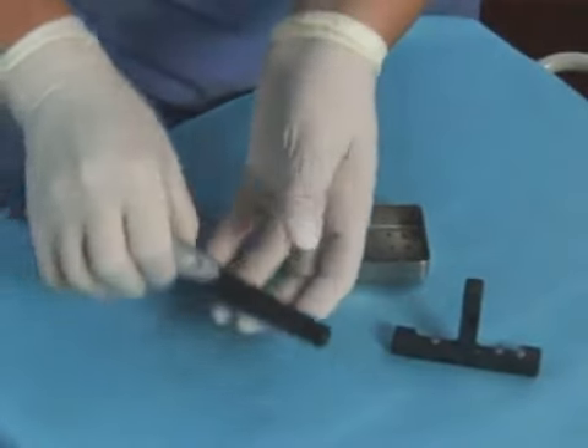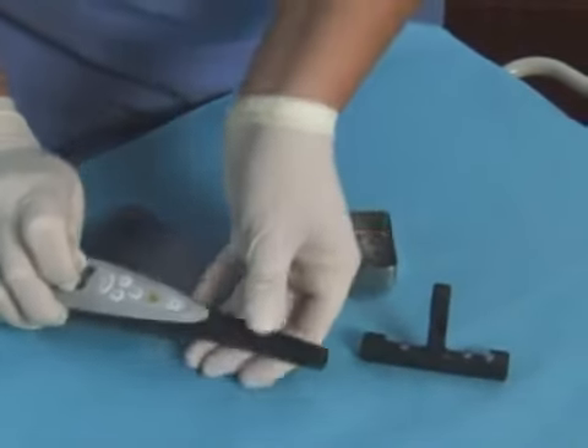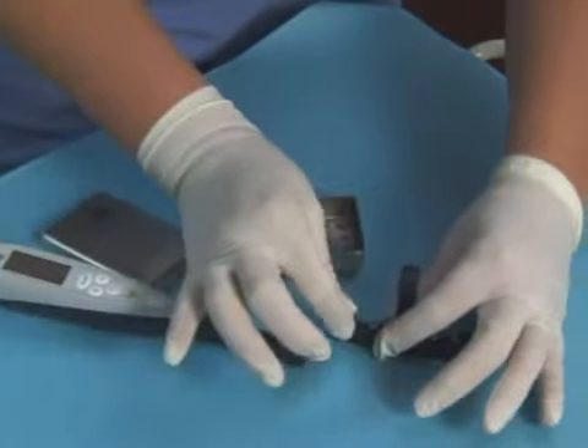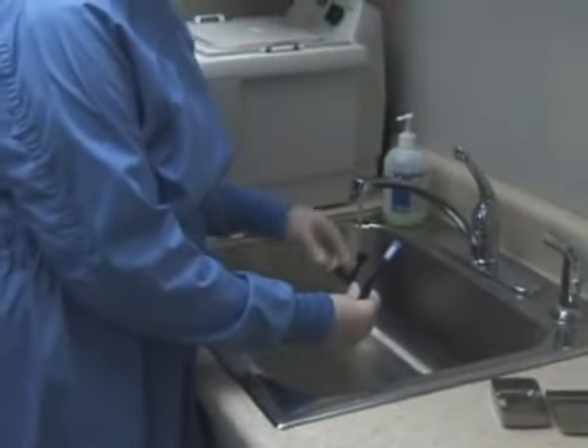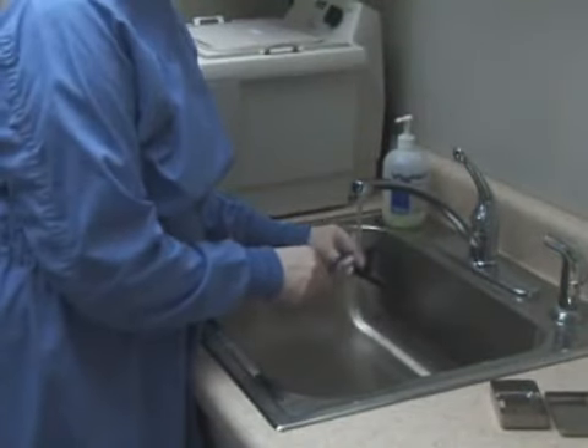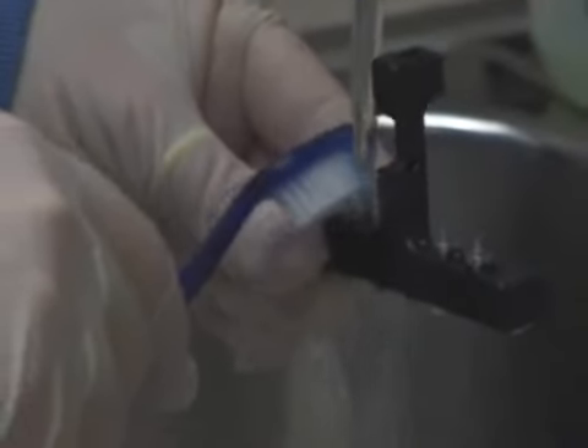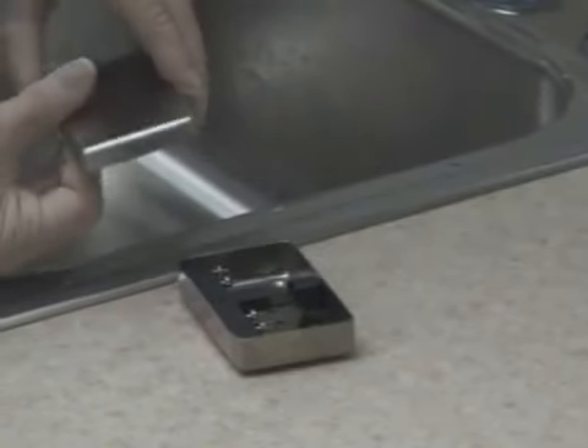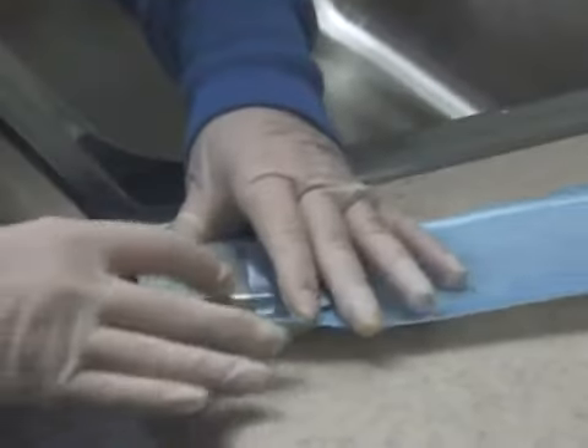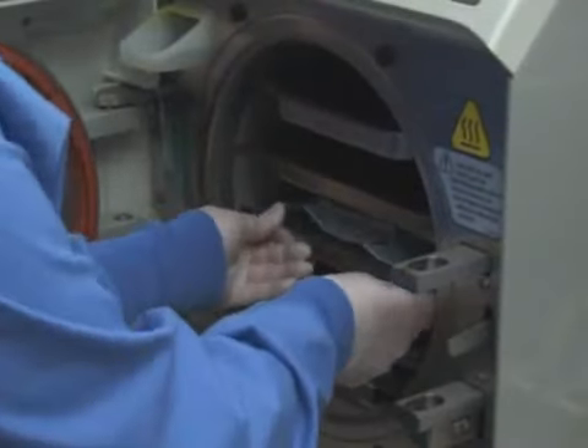After clinical use, remove the laser tip and place into the sterilization cassette holder. Scrub the tips under running tap water with a soft brush to remove debris. Place the tip holder in the sterilization cassette with or without calibration disc in place and autoclave up to 275 degrees Fahrenheit, 135 degrees Celsius.